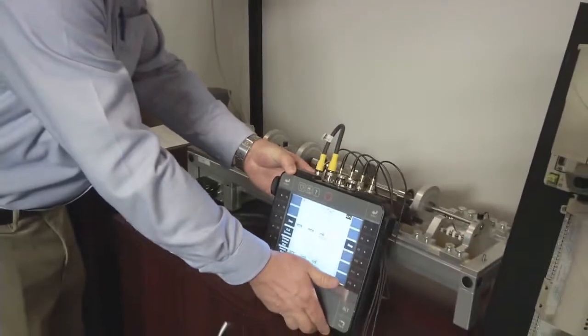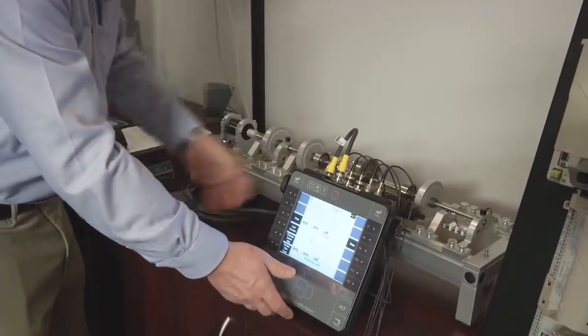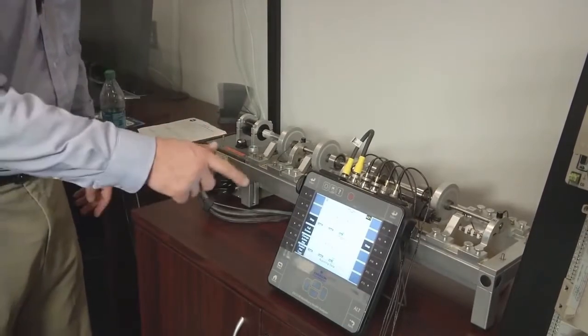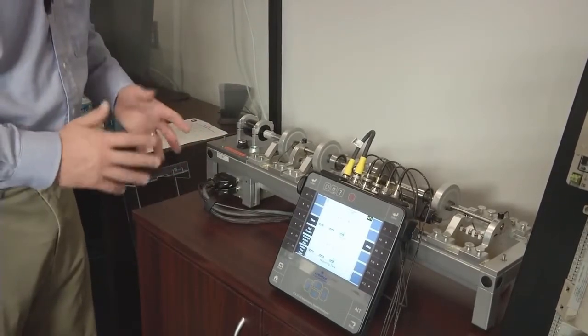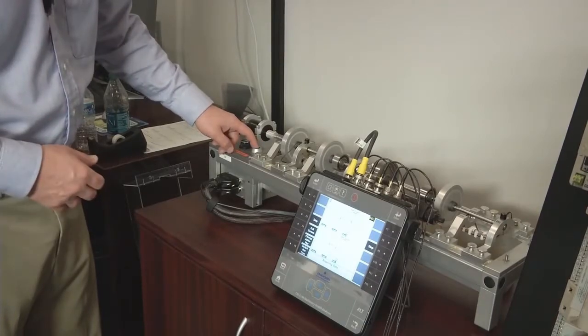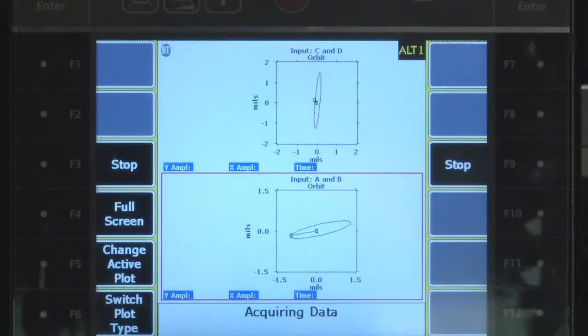I'm going to set this 2140 down here on the stand and just demonstrate these live orbits, how they will change in shape just by killing the power to this rotor. So it's coasting down now and you can see the shapes are decreasing with the speed. As I add the power back, you can see they come right back to where they were previously.